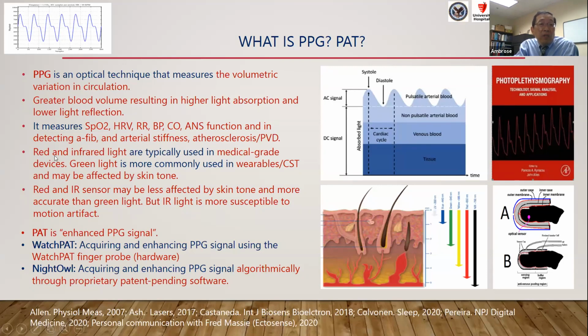It's important to know that different lights are used: red light, infrared light, and green light. Some devices use all of them. The red and infrared light are typically used for medical grade devices. They penetrate a little bit deeper and get better data in terms of vascularity and volumetric circulation measurement. The green light, however, is more commonly used in wearable devices. Most of the cheaper wearable devices have only green light.